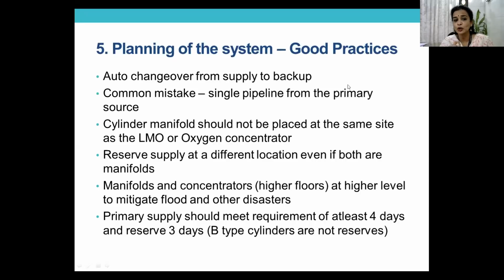The cylinder manifold should not be placed close to the LMO or even close to your oxygen concentrator. It has to be away from that. Reserve supply should be at a different location; even if both are manifolds, you need to have the reserve supply available. Manifolds and concentrators can be kept at higher levels, not in the basement, particularly in areas where you have floods. And we all know the example of Miot Hospital and what happened during the Chennai floods.